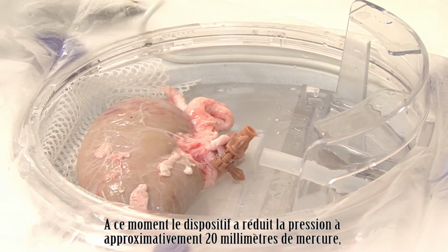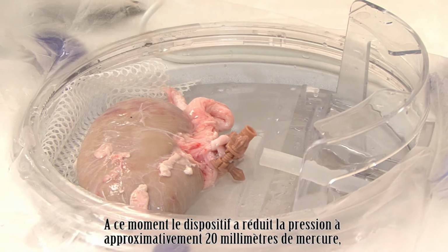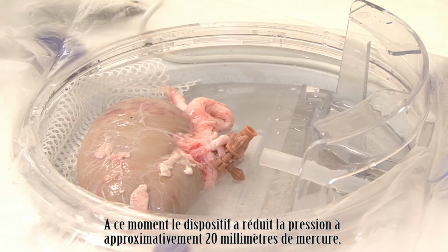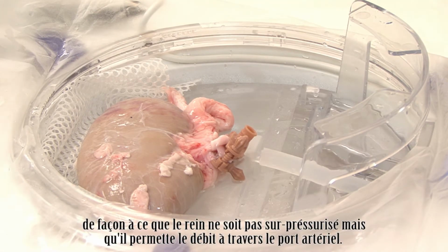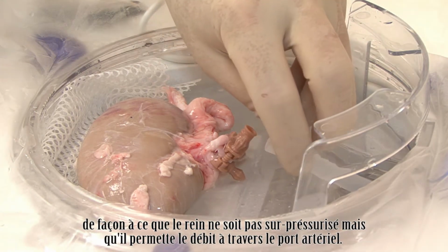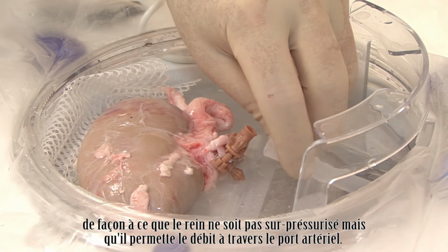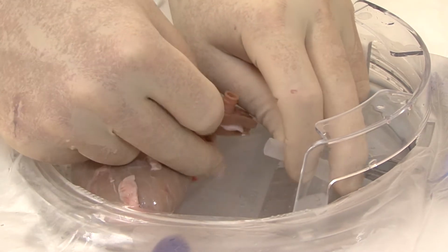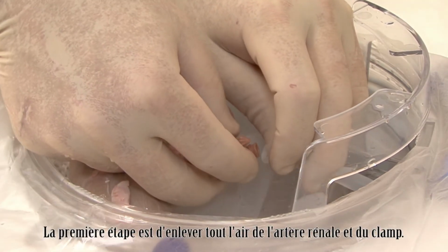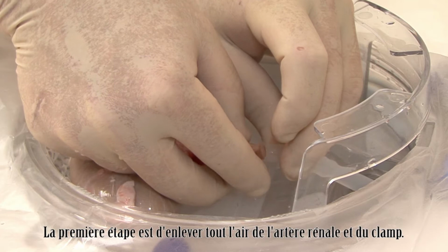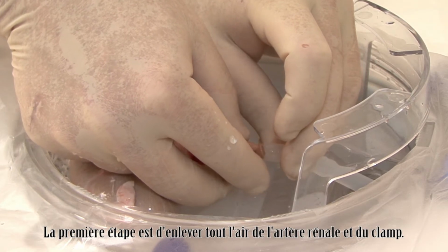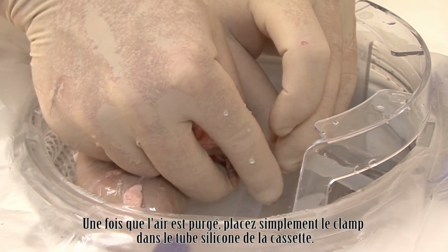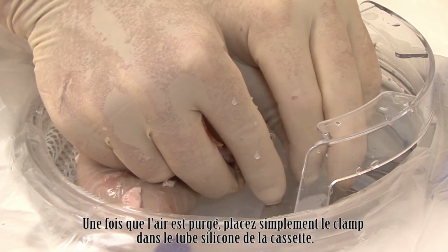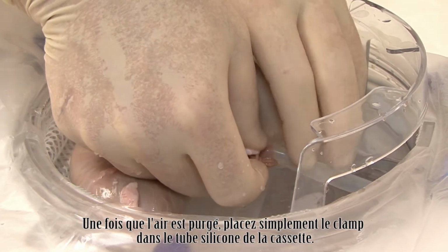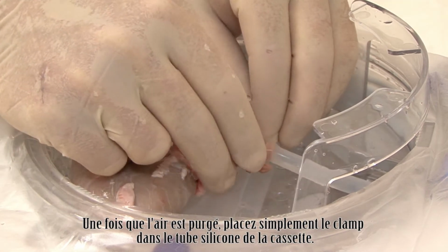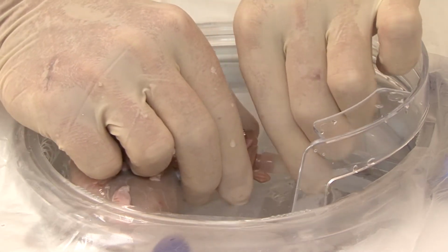At this point, the device has reduced the pressure to approximately 20 millimeters of mercury so that the kidney will not be overpressurized, but it does allow for some flow through the arterial port. The first step is to remove all air from the renal artery and the clamp. Once the air is purged, simply place the clamp into the silastic tube.